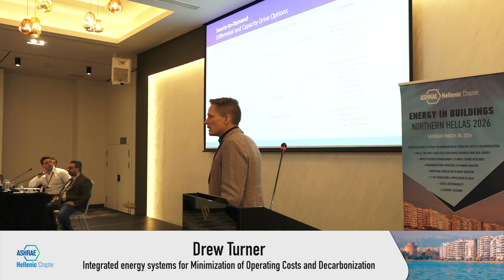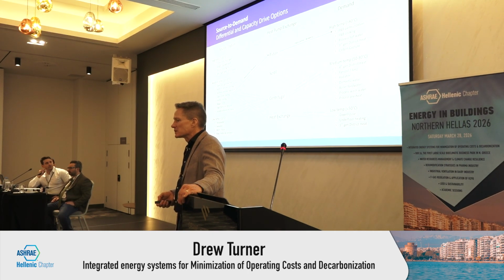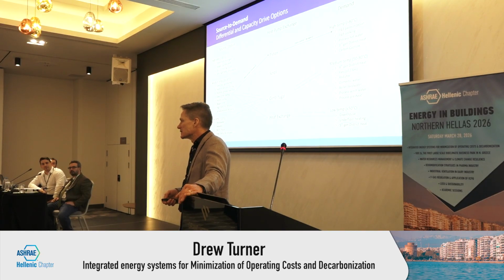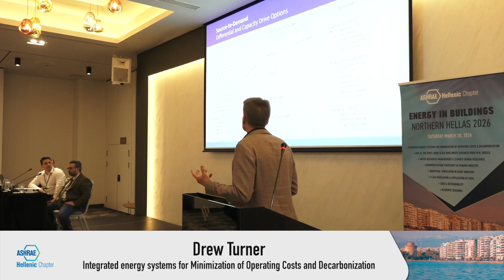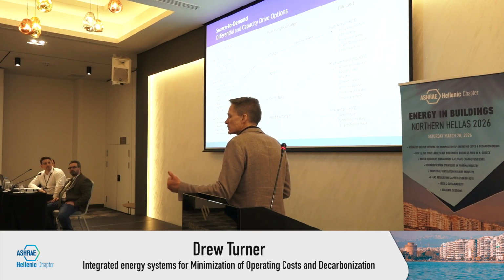In district energy, I've had a couple of conversations about district energy in the last day. The trend in the last 30 years in Denmark is to lower district energy temperatures, but they can do it at about 1 K per year. If you have a district energy system, you have to change out radiators to fan coils to underfloor, and do all of those changes that lower the temperature requirements that then drive ultimately the lowering temperature of the district energy system itself. It takes a long time if it's an existing system. So when we have these conversations, one of the first ones is, can we also explore the end devices, both on the cooling side and the heating side, to change the operating temperature profile, to make this decision the last decision to then drive the most efficient system.